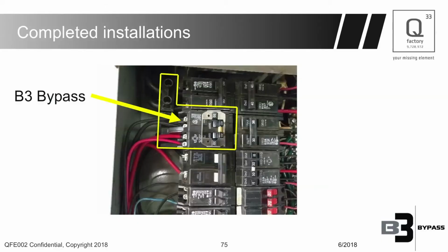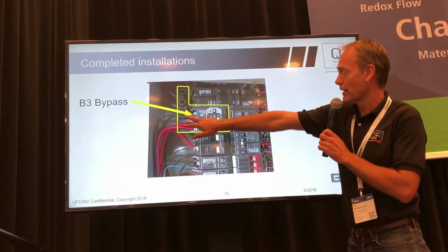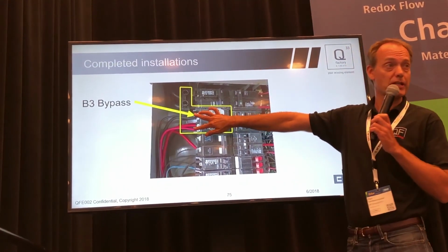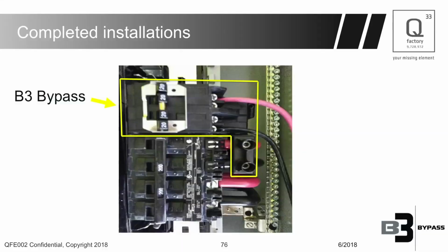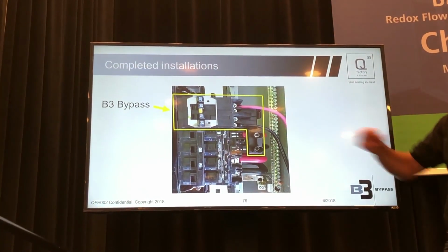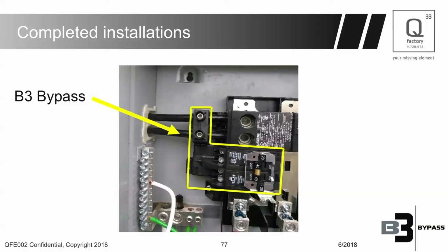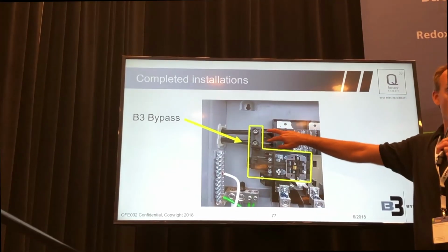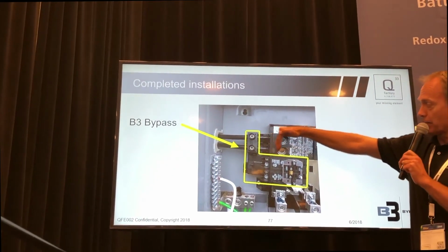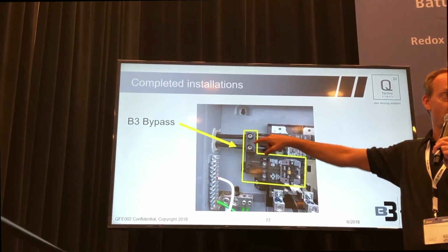I have some sample installation photos that we'd like to show you here. So, a 100 amp main breaker right here, the B3, and here we have 2 different generation sources attached to it. Another example here: B3, 200 amp main breaker, and we have 1 generation source added to that. Different configuration. This shows the Siemens QN, and you can see how we need more unbent feeder wire here because the breaker's recessed a bit. So we need around 1.5 inches of unbent feeder wire.